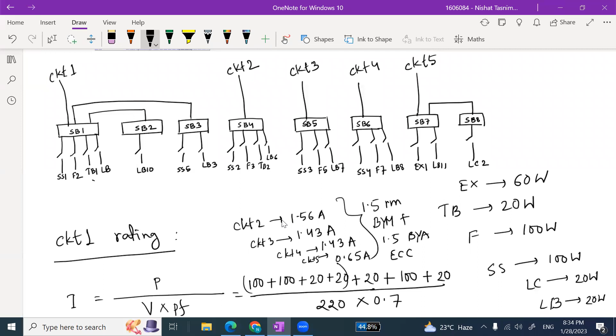What is the current in circuit 3? Ma'am, 1.43. Yes good. Circuit 4, ma'am 1.43, this is also 1.4. And circuit 5, 0.65 ampere. So as you can see, all the amperes are below 5 ampere. So for all this we can use the same cable, that is 1.5 RM BYM plus 1.5 BYA ECC.